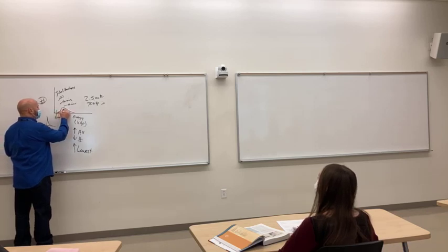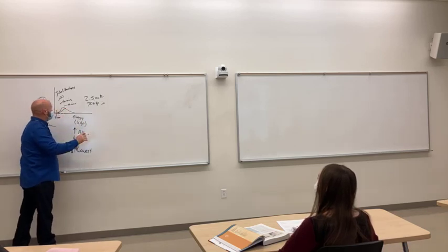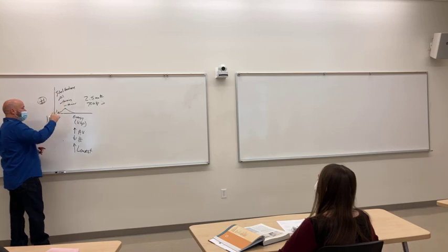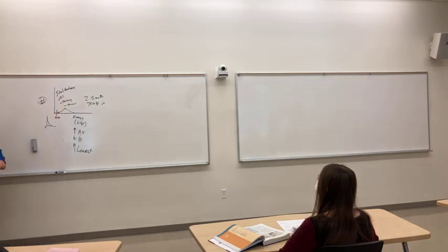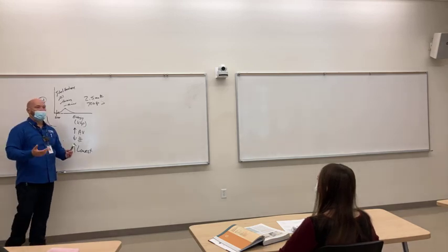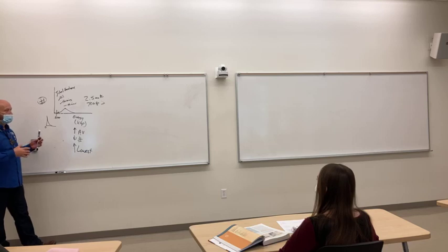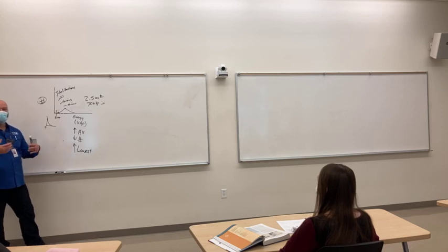This average goes that way towards the high energy side, and our numbers continue to decrease. Okay? So if I continue to add filtration, would that come with radiation safety implications for the patient? Yes. Absolutely. Increased filtration, you're going to continue to decrease patient dose.